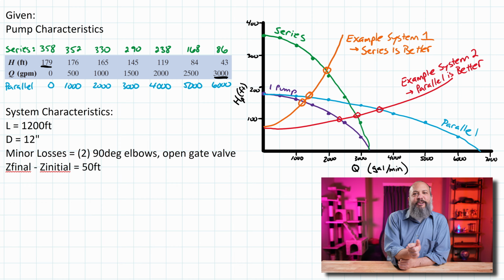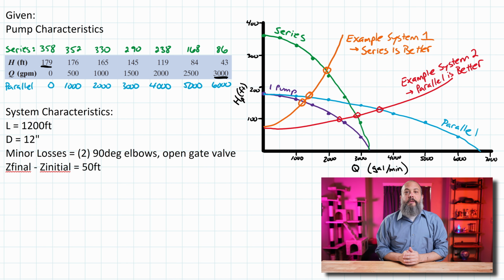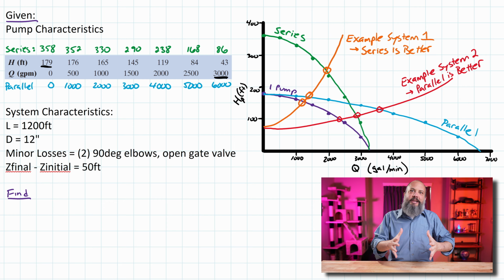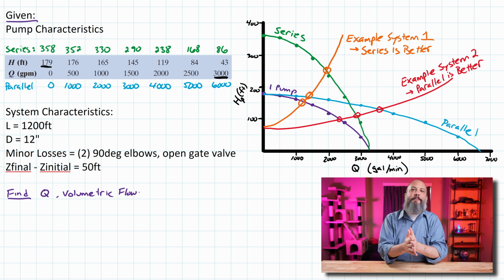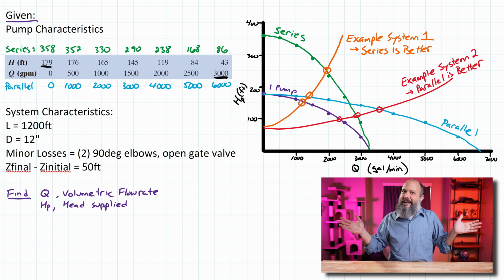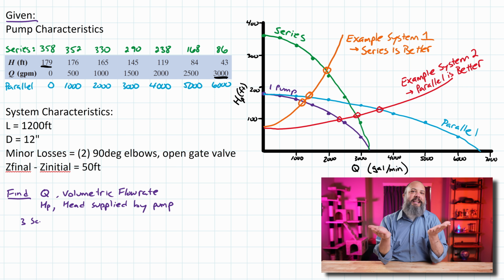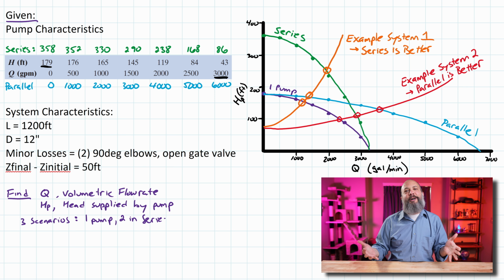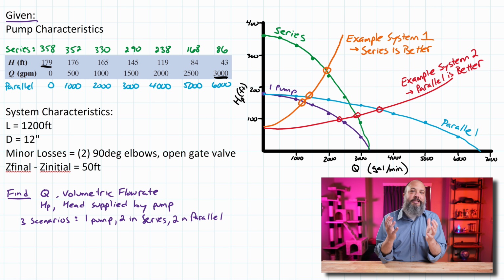And in fact, the series and one pump actually behave kind of similarly at high flow rates, low pump head. Okay, so now we sort of understand series and parallel pumps and what we're looking for when we compare the system curve. So we need to actually draw the system curve, and that's where basically all of the work comes in, is in understanding your system.